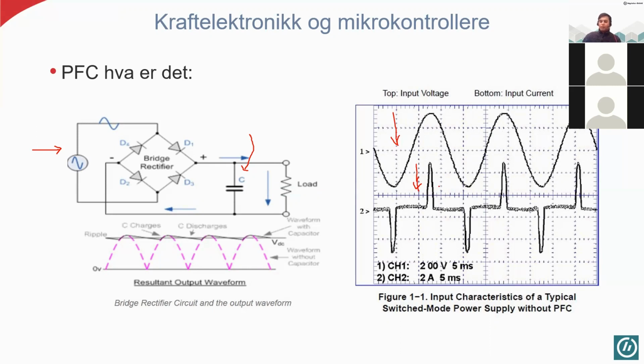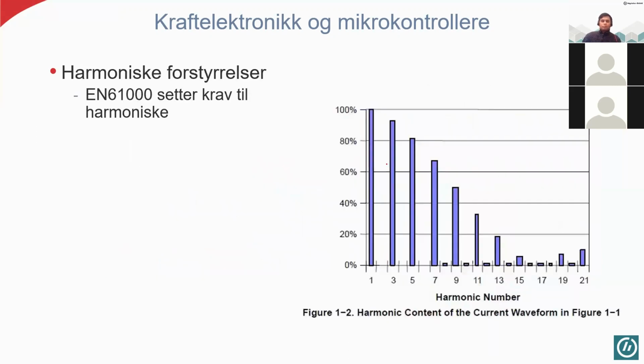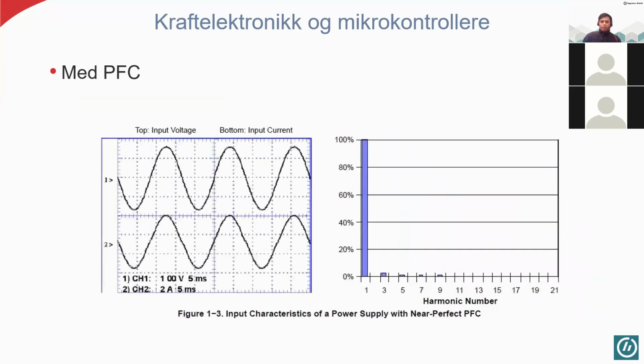You know the different orders of harmonics - second order, third order, fourth order, and so on. So we have the standard EN61000. For example, if you apply for the CE mark, you have to pass this standard for your product, then only they will give you the CE mark. So this standard gives us values for each device, what is the allowed or permitted amount of harmonics. This is also important when we talk about power factor.